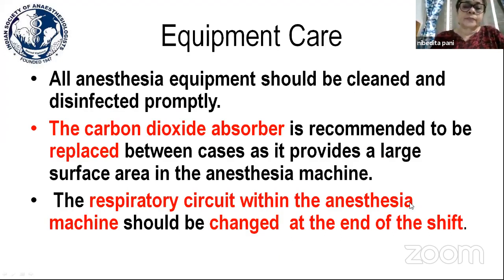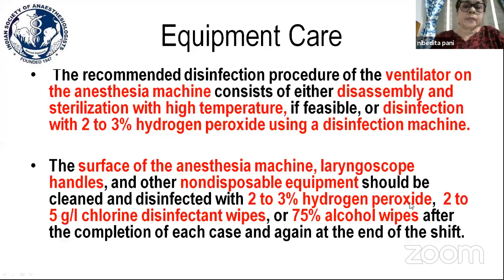How will you disinfect the ventilator of the anesthesia machine? The recommendation is that either you disassemble or sterilize with high temperature, if feasible, or disinfect with 2 to 3% hydrogen peroxide using a disinfection machine. The surface of the anesthesia machine, laryngoscope handle, and non-disposable equipment can be disinfected with 2 to 3% hydrogen peroxide or 2 to 5 gram per liter chlorine disinfectant wipes, or if nothing is available, the easiest is 75% alcohol wipes, which we commonly use.